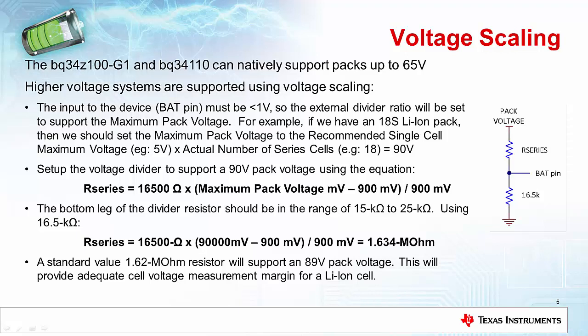For example, in these systems, we need to have a voltage divider here such that we reduce the voltage that is being measured at the BAT pin down to less than 1 volt. And so the divider has to be able to take whatever your maximum voltage is and divide down to that level. For example, if we have an 18S system, then maximum pack voltage will be somewhere around 4.5-ish to 5 volts times 18, so 90 volts is kind of an upper level maximum. So if we want to take 90 volts and then divide that down to less than 1 volt, let's say 0.9 volts, we can calculate that out to see what resistors we need in that.